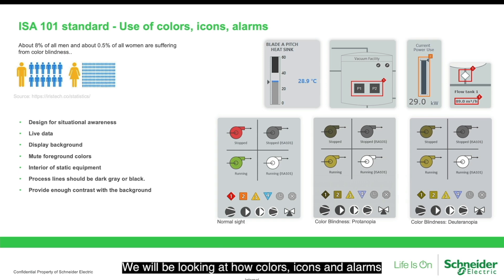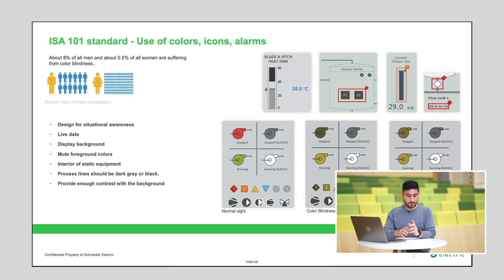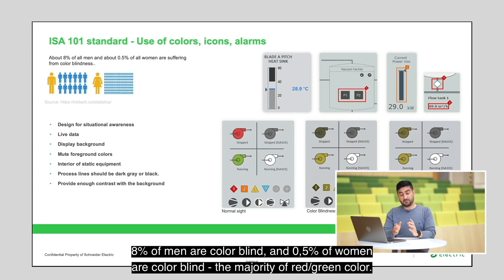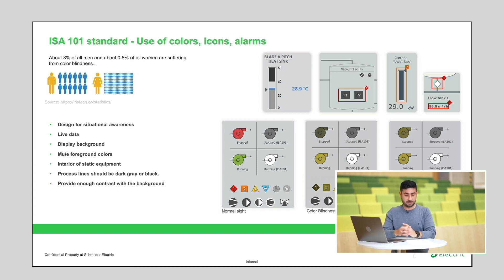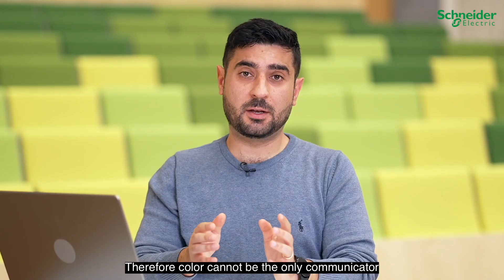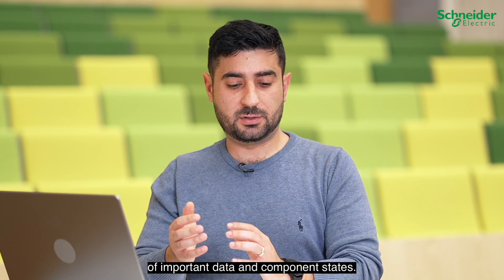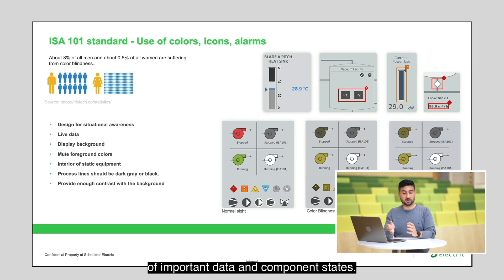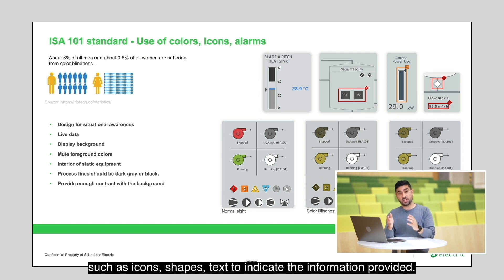Now that we have looked at how you can structure the hierarchy of your displays, we will be looking at how colors, icons, and alarms are used in ISA 101 standard. Eight percent of men are colorblind and 0.5 percent of all women are colorblind, the majority being red-green colorblind. Therefore, color cannot be the only communicator of important data and component states — it should be combined with graphical elements such as icons, shapes, and text to indicate the information provided.